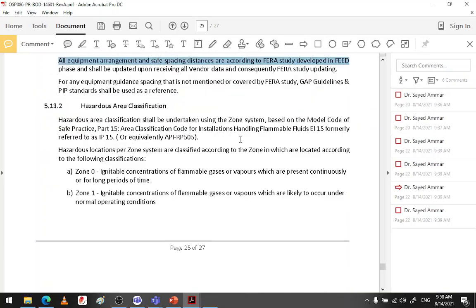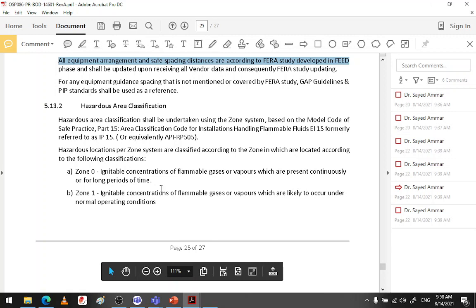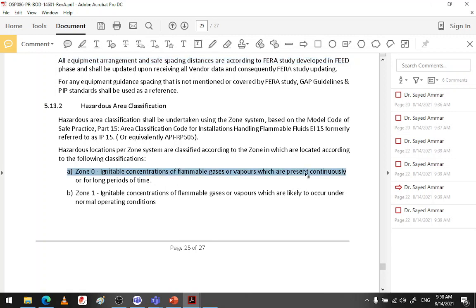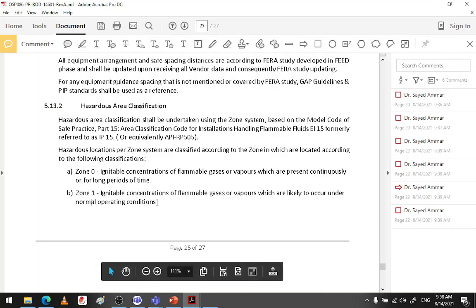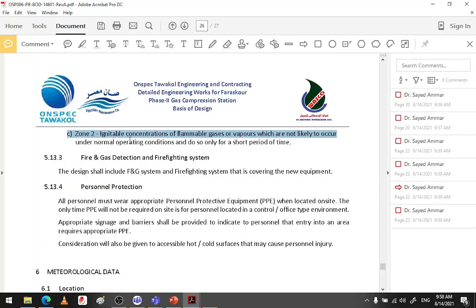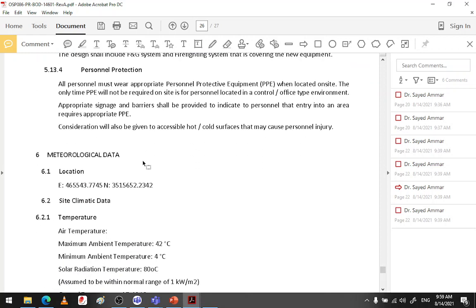Hazard area classification used for this plant will be according to IP15 or API 505, which is both. Zone 0, ignitable concentration of flammable gas. Zone 0 is continuously persisting, the main process area. Zone 1, the vapors are likely to occur under normal operating conditions, like tanks. And Zone 2 for the utilities like the instrumentation, air, power generation, and all of this. We didn't have any flammable gases there.